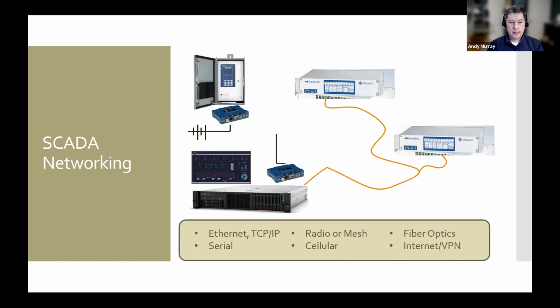So the SCADA network - I don't know if I mentioned this before - a SCADA system is typically what you'd refer to as a wide area network, since it's expected to communicate with substations. Even a small municipal utility I work with might cover 1, 2, or 3 towns, so you're talking maybe 2, 3, 4, 5 different locations, possibly with pole-top devices. So the SCADA system is a geographically dispersed system, as opposed to a DCS system, which would be expected to be within one plant, one building. Even if an entity owns several generating facilities, they'd have a separate dedicated DCS system at each plant.